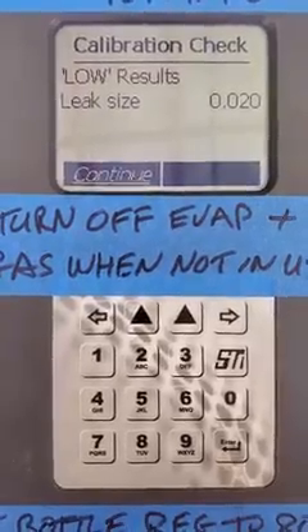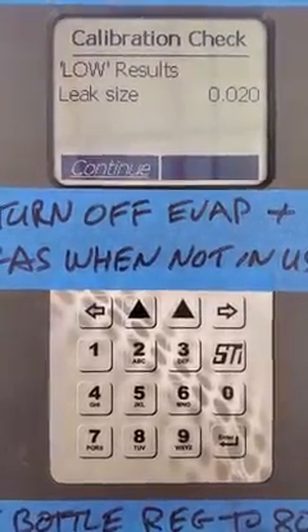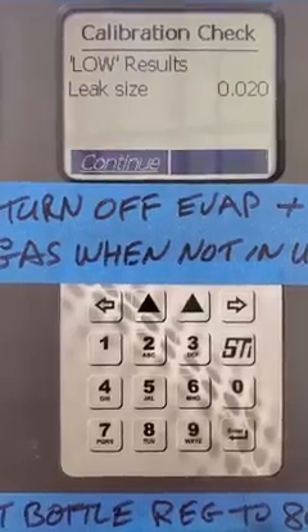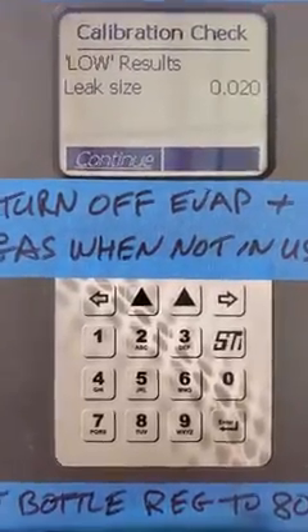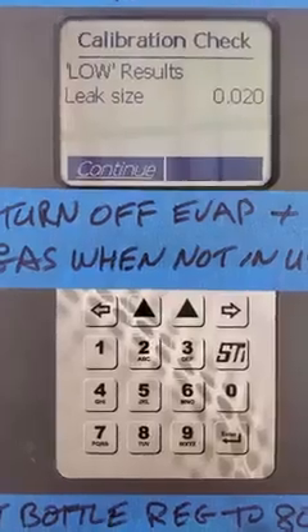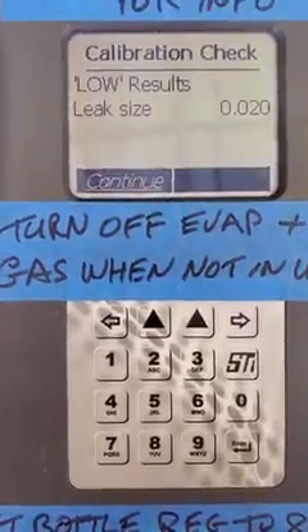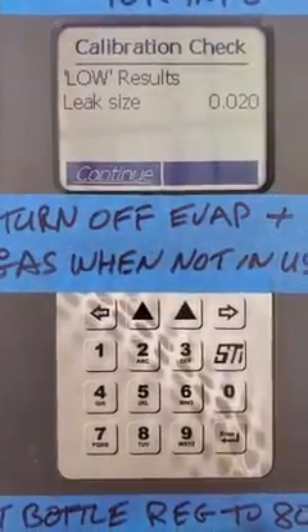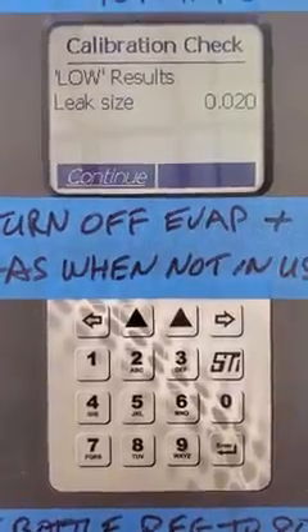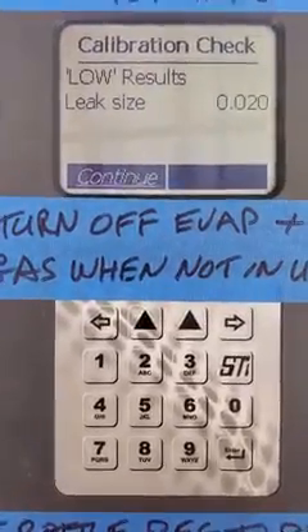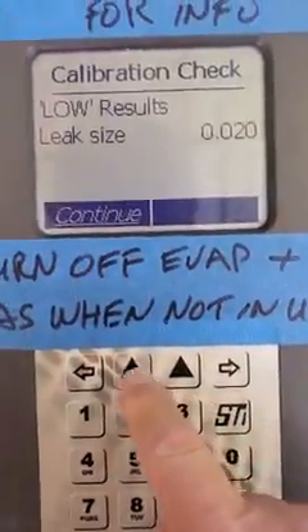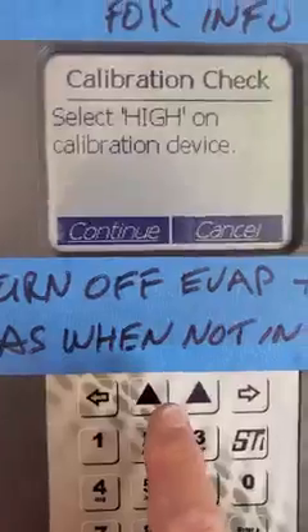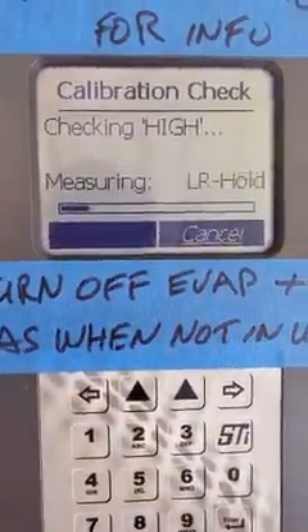So the low result should be 0.02. As you can see, this machine is right at 0.02, but you know, 0.017, 0.018, 0.022 would be considered normal. So push continue, turn your valve to high, and start the high side of the calibration.